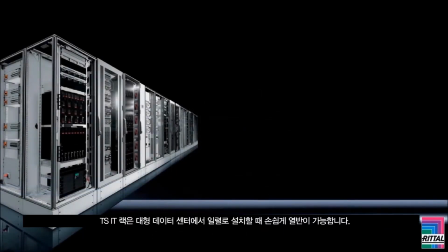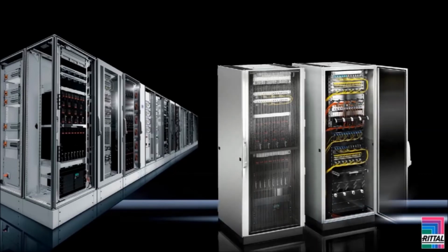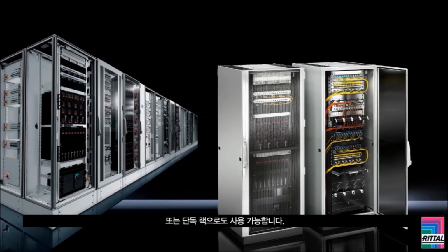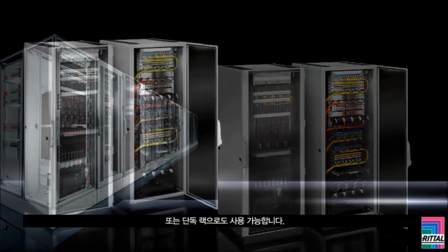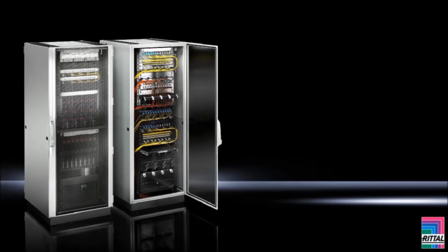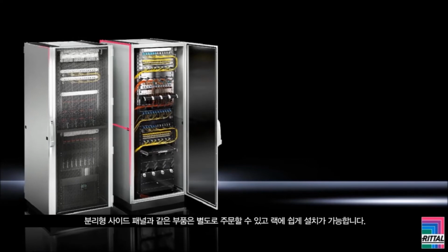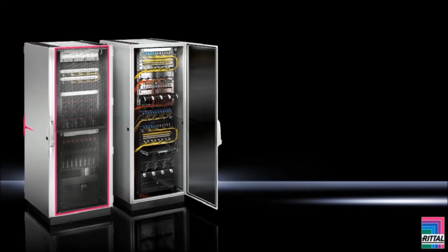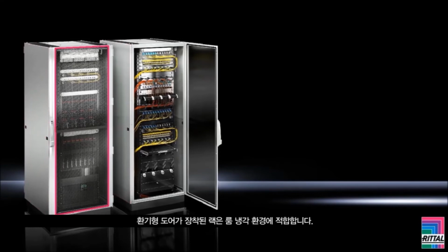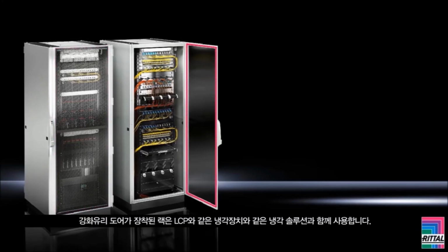The TS IT rack can easily be bayed to form rows in a large data center. Or, it can be used on its own as a freestanding data center in a rack solution. Parts, such as the divided side panels, are ordered separately, making it easy to equip the rack according to your needs. The version with a perforated door is suitable for an air-conditioned environment, while the glazed door would typically be used with a rack cooling solution, such as the Rittal Liquid Cooling Package, or LCP.